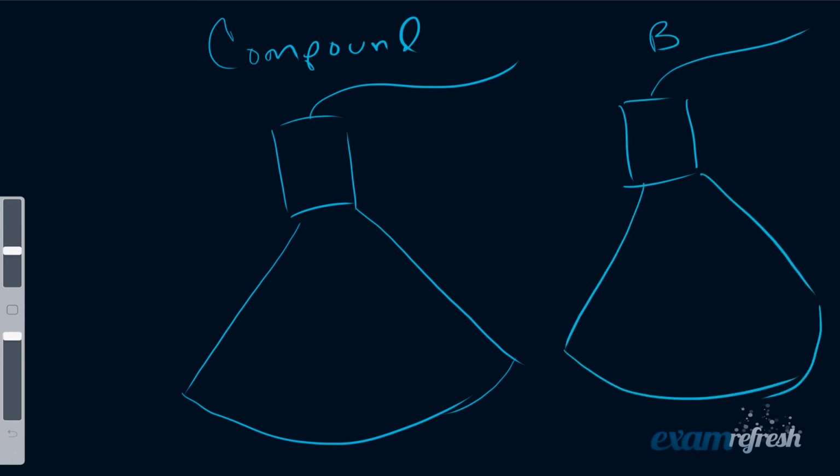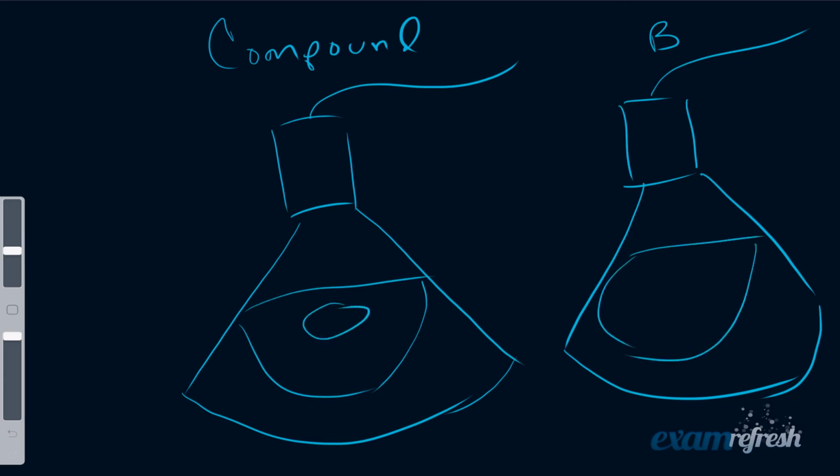So with our compound image compared to our B-mode image, this is what can happen. Let's look at if we have a mass here. So let's draw out a liver here. Just imagine you're looking at a liver here on a generous patient. That liver's kind of way back there. So we have our mass here. And in general, with B-mode imaging, that single angle of insonation will probably create shadows on the edge of that mass. So if you have that shadow, that may be hiding information.